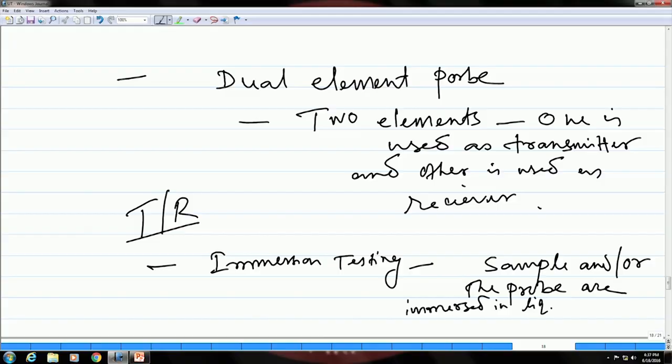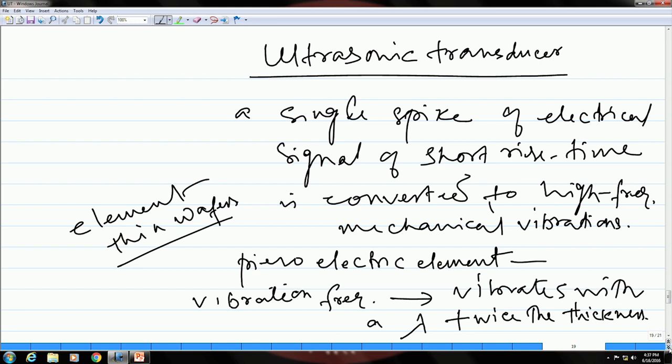That is how the dead zone can be taken care of. We then started talking about ultrasonic transducers — what are the components and how ultrasonic pulses are generated. In an ultrasonic transducer, you supply a single spike of electrical signal and convert it into high frequency mechanical vibrations or ultrasonic pulses.